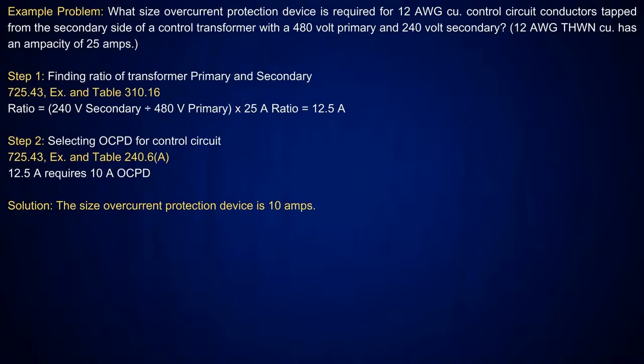Okay. So what I need to do, and you'll remember this, when we're tapping, I said always when you're tapping, you've got to get what? The ratio of the transformer. So I would take the 240 volts divided by the 480 volts. We're telling you here that the number 12 has an ampacity of 25 amps. So take that ratio of the transformer times 25 amps. That's going to give you 12.5 amps. And then I'll drop down to the next standard size overcurrent device.